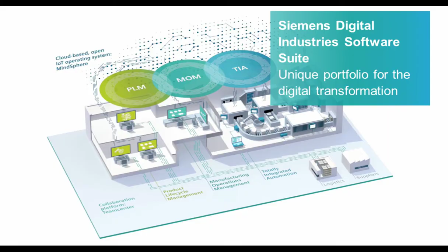With third-party controllers using OPC, you must have a physical PLC beside it. There are no virtual PLCs on the market now that can do what we're doing. It would all require what we call hardware in the loop, a physical PLC, and while that's possible, you have to ask how you'll handle the safety and the high-speed synchronization. Overall, it's just going to be an easier solution with the Siemens setup, but definitely possible with third-party controllers too, as I showed in the video during the session.